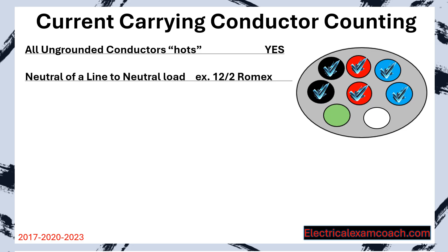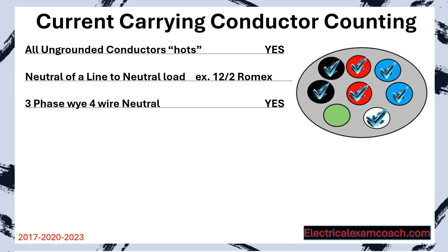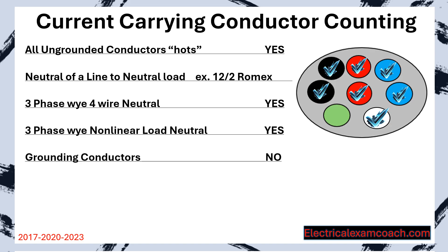The second one is the neutral of a line-to-neutral load — meaning if a light bulb draws one amp on a 120-volt circuit, there's one amp going in on the hot and one amp flowing back on the neutral, so it is a current carrying conductor. Same thing with a three-phase four-wire neutral and a three-phase non-linear neutral load — non-linear loads come from large fluorescent lighting or large computer data centers. Grounding conductors do not count.